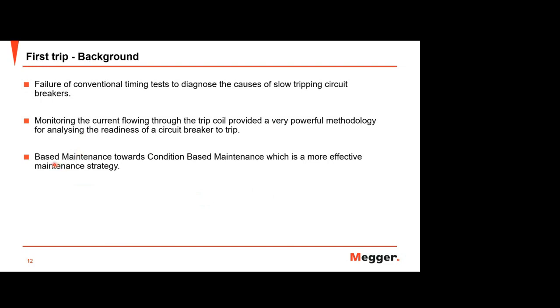And also, you can use this method as a base to move from time-based maintenance toward condition-based maintenance, which is a more effective maintenance strategy. So this is the background story of why we have the first trip, because sometimes conventional testing cannot reveal some issues in the real condition of the circuit breaker. So they are still missing some information when doing conventional testing. This is why the first trip can be used as additional information, or as just one test to get more information, especially for a circuit breaker that has never operated for a longer time, maybe 5 years, 10 years in idle condition. First trip is more preferable for testing, because it can give you real information.